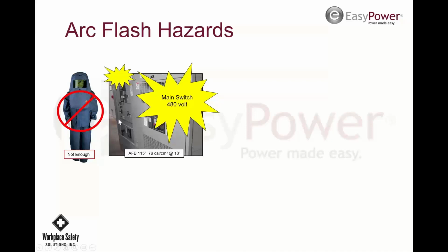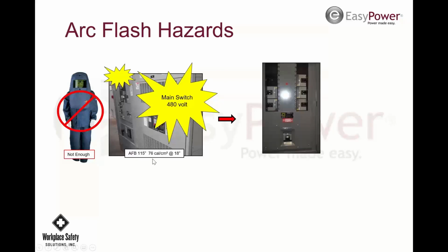So what they did was they asked the utility to replace the transformer, of course at a cost, and they replaced it with a 1500 kVA transformer, and it brought it down to 28 calories from where it was. So that was a big change in the available fault current and so forth. Okay, and what it is now is what it is. So that's what they're dealing with.